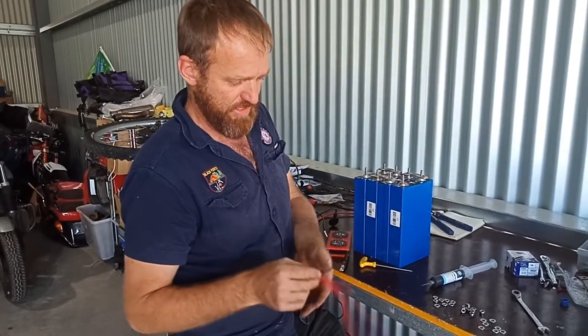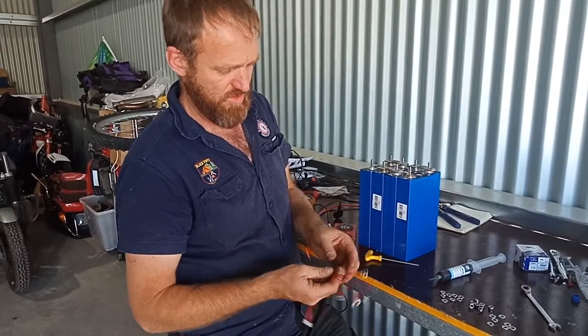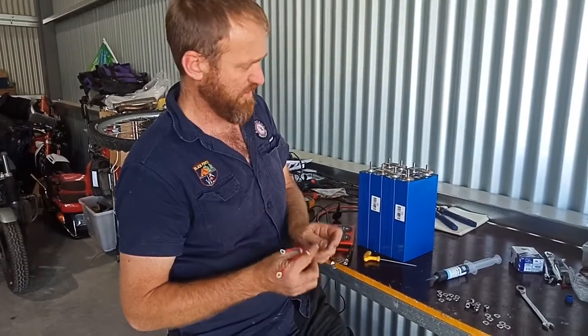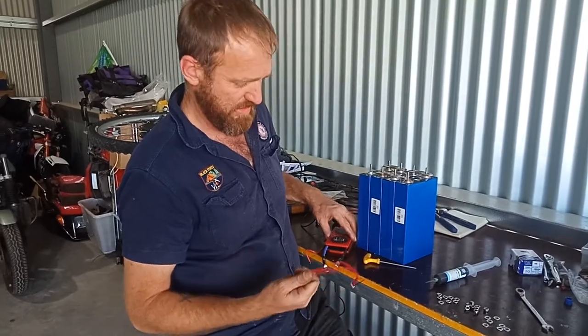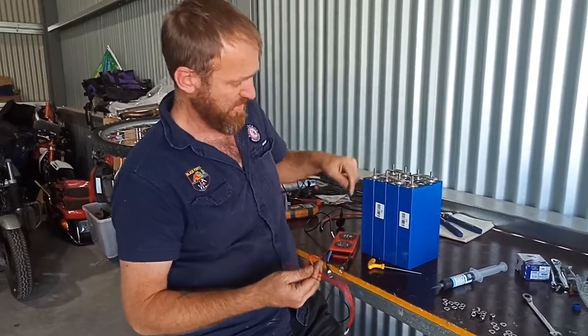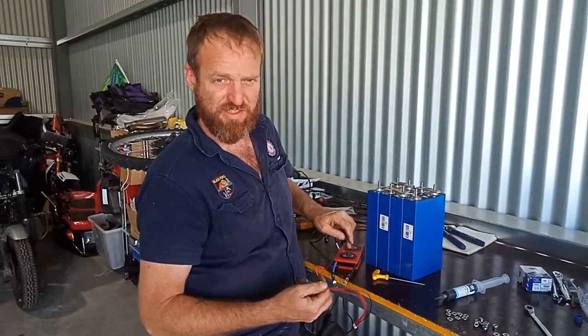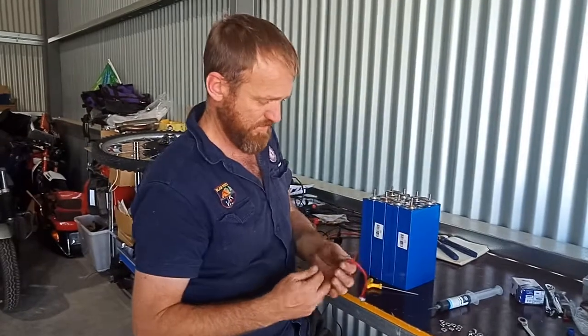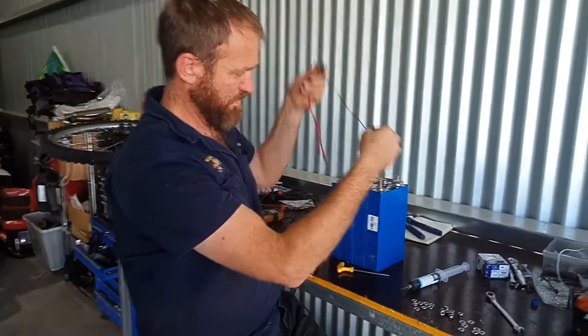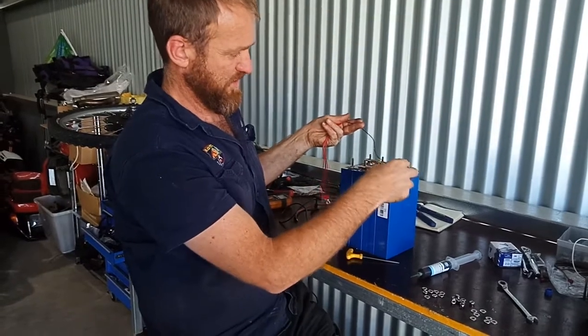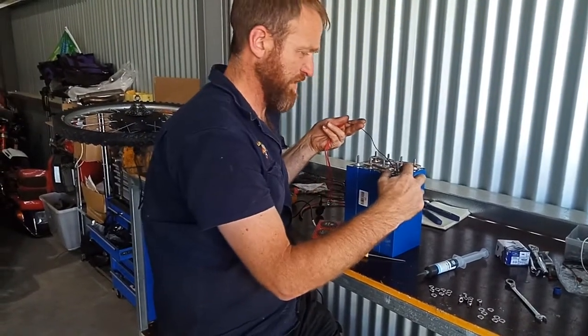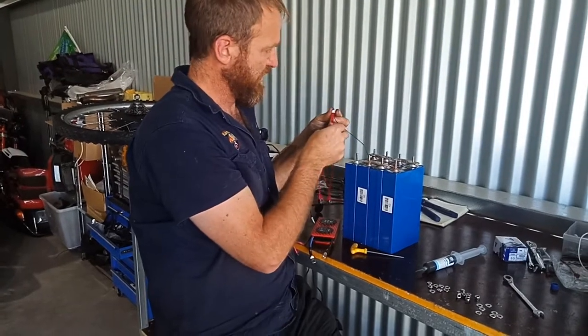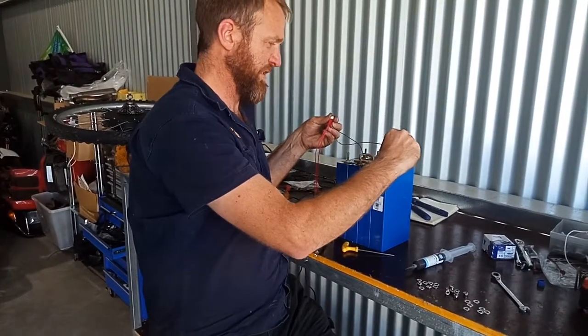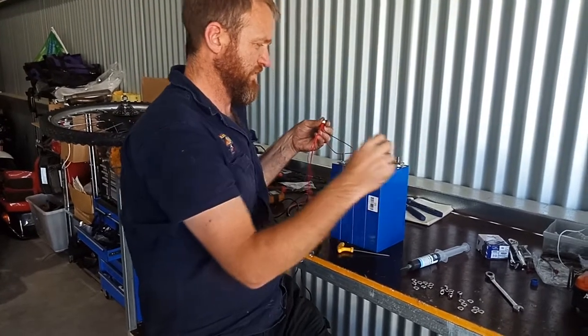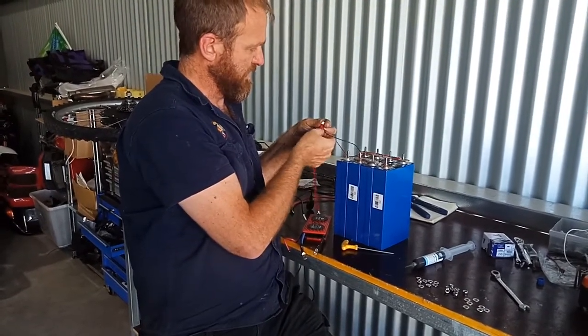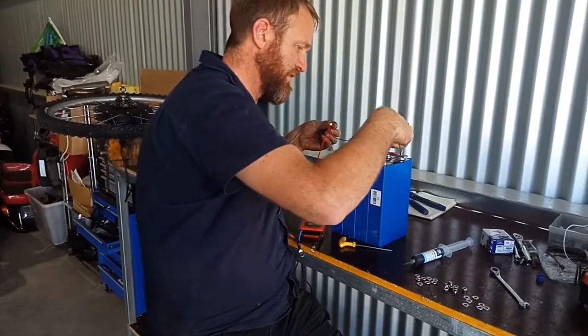But they need to connect to the battery, so we start with these lines, and we always start with the negative first. If this is plugged in and you start with the positive first, with negative connected last, you can either blow the wire or blow the internals on this, because the MOSFETs will see reverse current. So we always start with the battery wires disconnected, start on the negative pole, which has a negative symbol and is usually copper, go to the next in the line or string, then to the positive terminal, and then next in the string again to the next positive terminal.